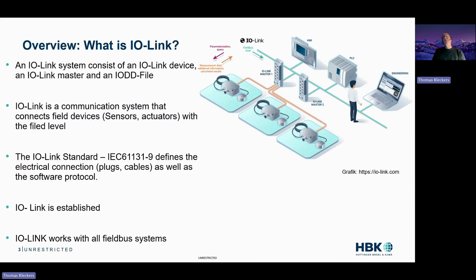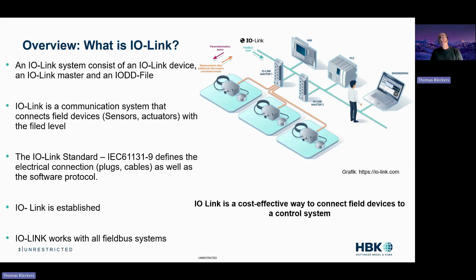IO-Link is a system for the field level, and the IO-Link devices are connected via cheap M12 cables to so-called IO-Link masters, which are the gateways from the field level, from the sensors, or it could be an actuator as well, to the PLC field bus system. IO-Link is defined in certain standards, so it is not an HBK invention, it's standardized on an international basis, and it's a quite cost-effective way to connect field devices to a control system.